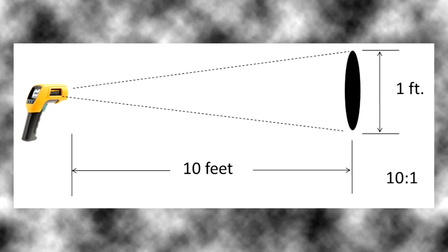For example if we had a device with a 10 to 1 distance to spot size ratio and we were 10 feet from the target we would take that 10 feet divided by the 10 to 1 ratio and that would give us a 1 foot diameter circle. So the laser would be pointed at the center of this one foot diameter circle and the IR thermometer would be measuring the average temperature of that one foot diameter circle.